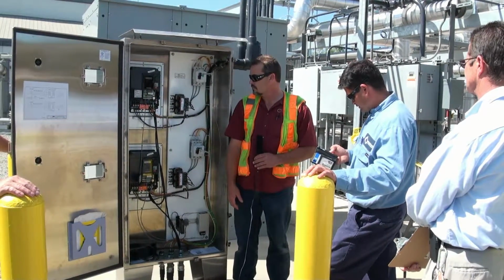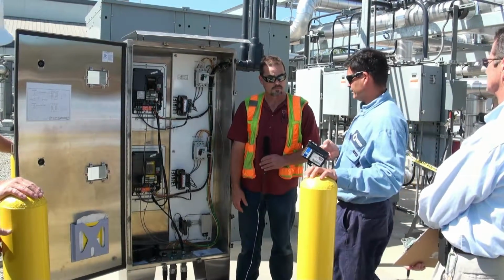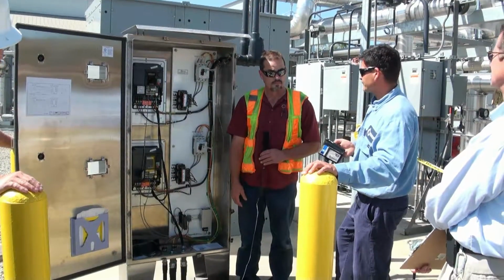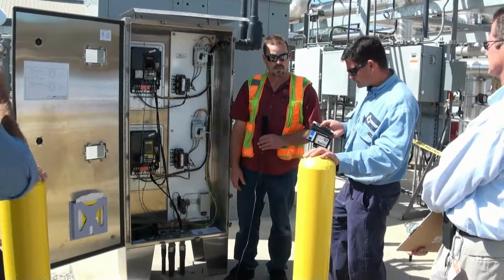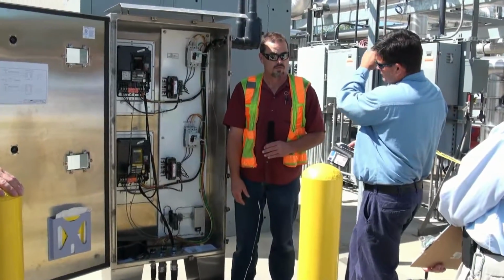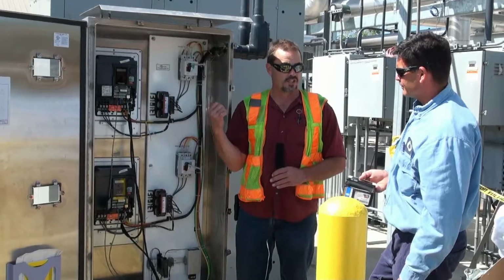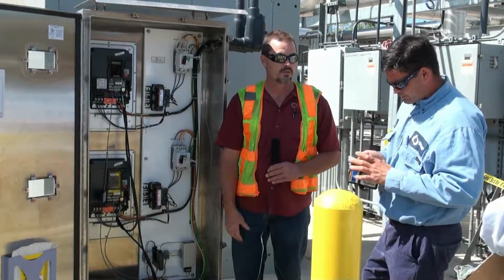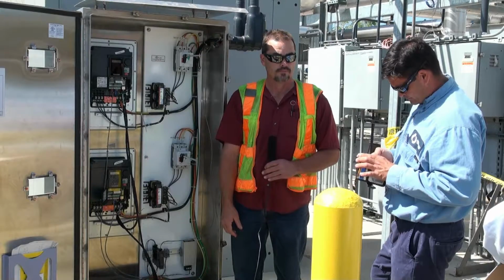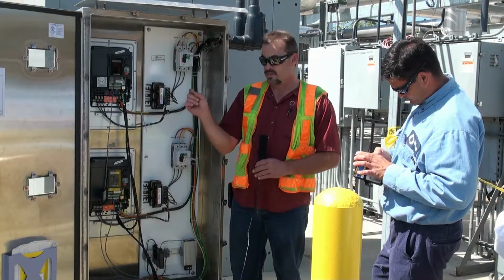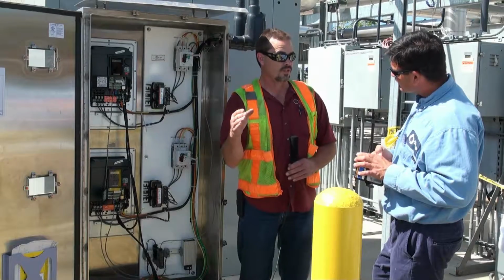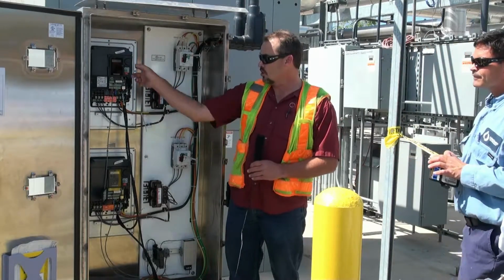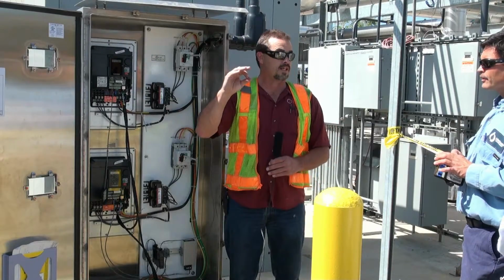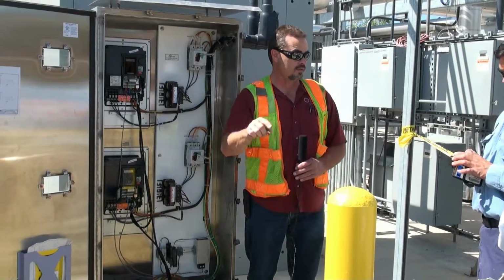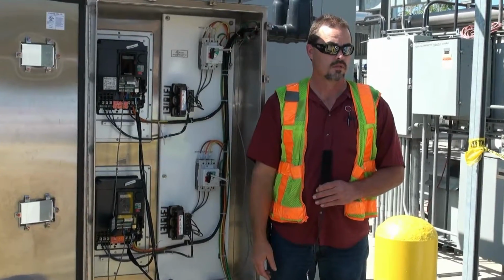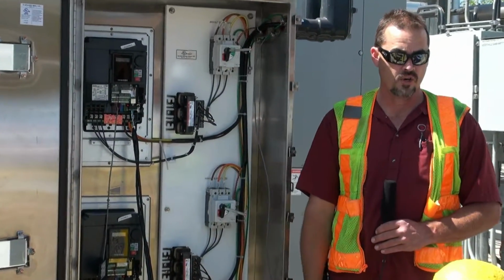So the red run button goes to green when it's in remote. Actually, when it's in auto, when they're controlling it from the BMS, it'll go to red when it's actually turning that motor. The green run button means it's ready to run when you tell it to. And if you put it in local remote, it'll be green because it's waiting for you to tell it to run. So we hit run, it turns red, turns it on. And now you know that it's turning the motor when it turns red.